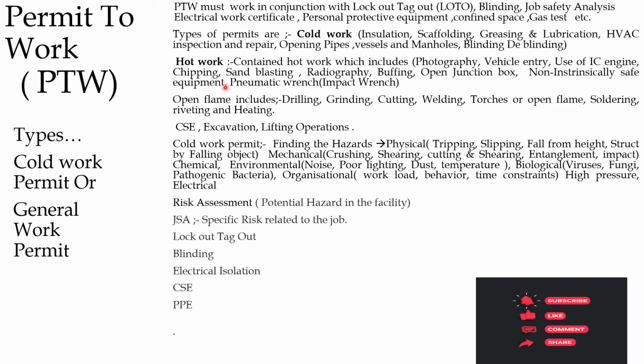Non-intrinsically safe equipment which will produce a spark when it is opened, or a pneumatic or impact wrench that is used — these all fall in the area requiring contained hot work. This is also done after a gas test and with proper precautions.